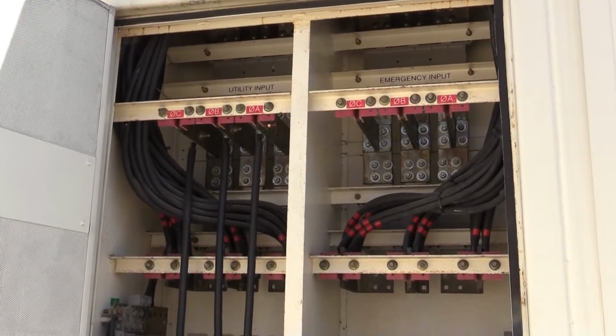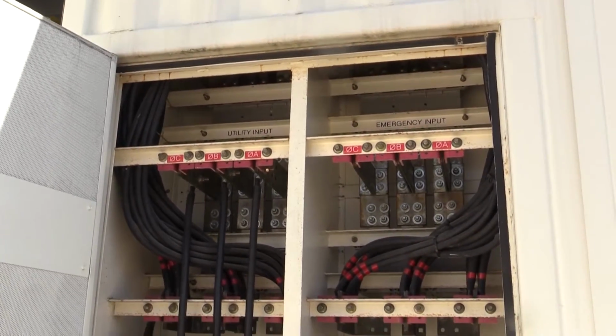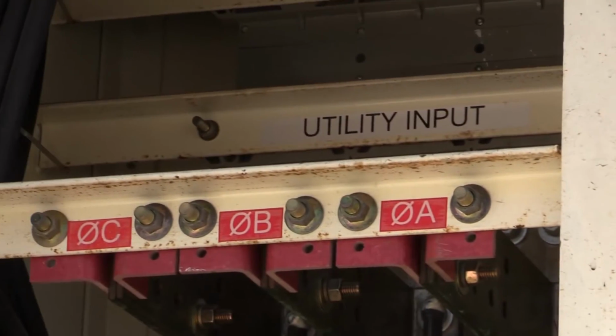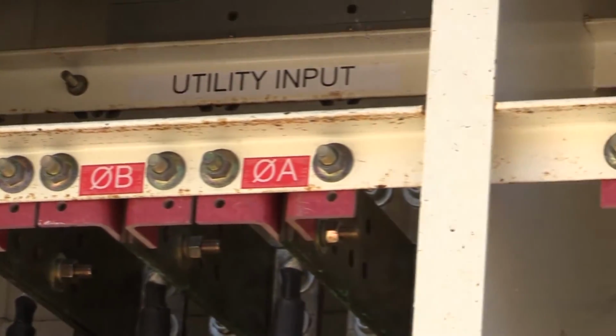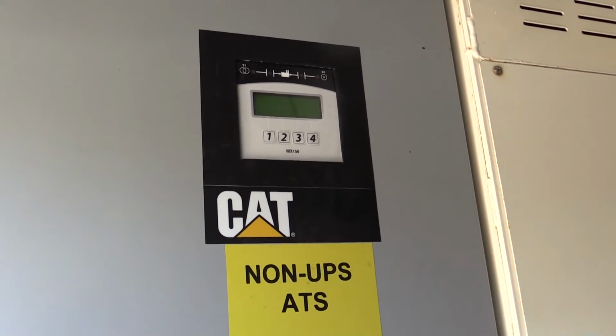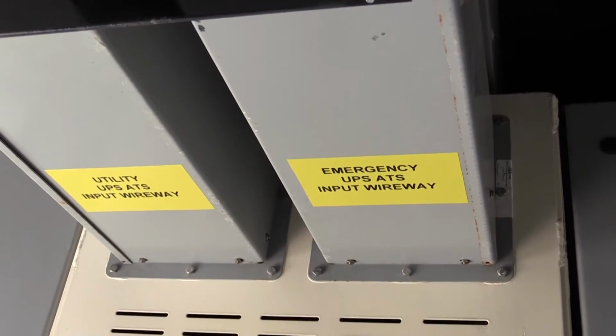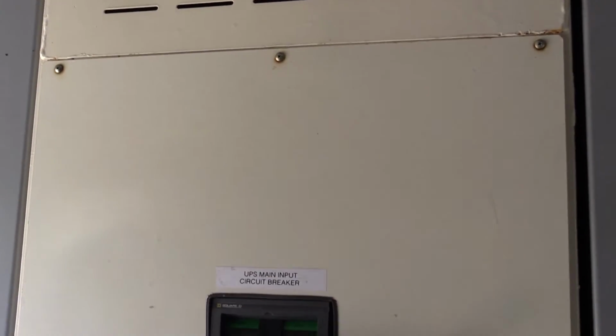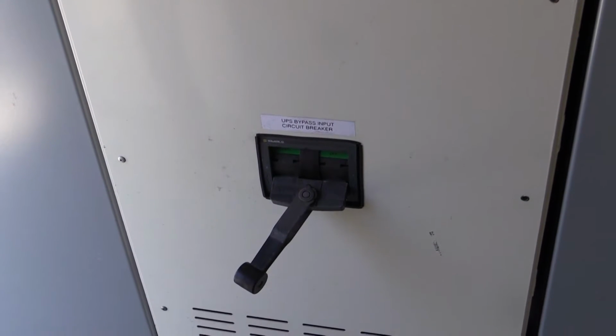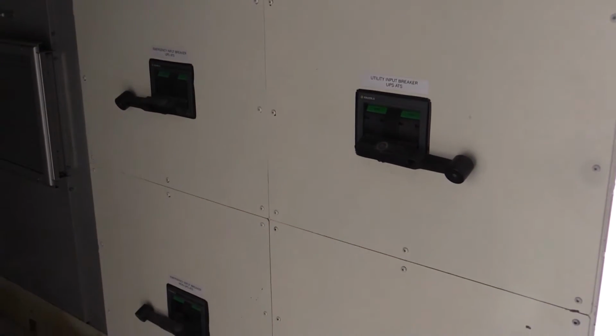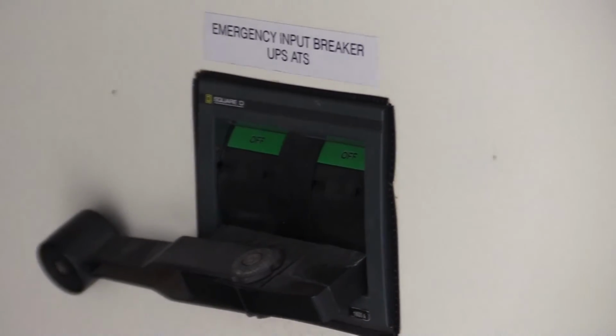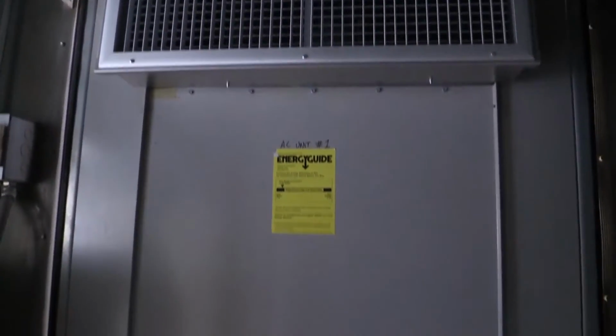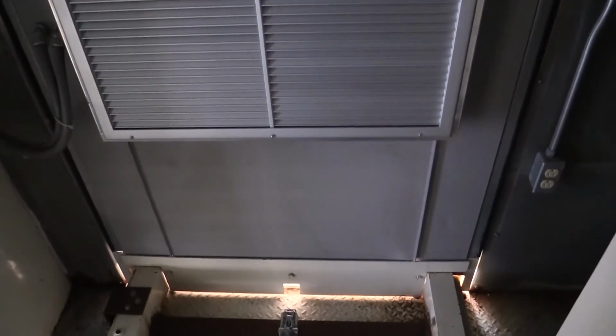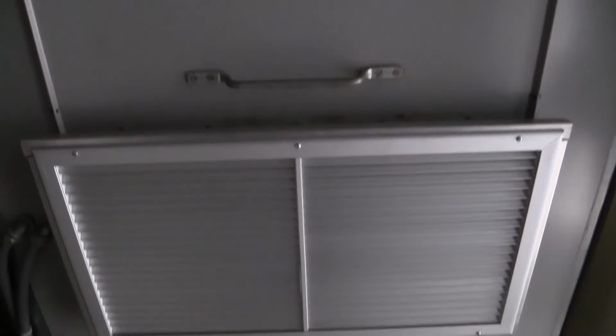We have a utility input and an emergency input. This is where we're going to hook up our utility source and our emergency generator source. We have two automatic transfer switches inside the Alban CAT Rental UPS. The first automatic transfer switch is going to control essential loads. The second is non-essential loads. We have multiple breakers inside the unit which control different sources and different outputs. All of our rental UPS systems are completely self-contained with their own temperature control system for air conditioning and heating. This maintains the humidity and moisture control inside the unit.